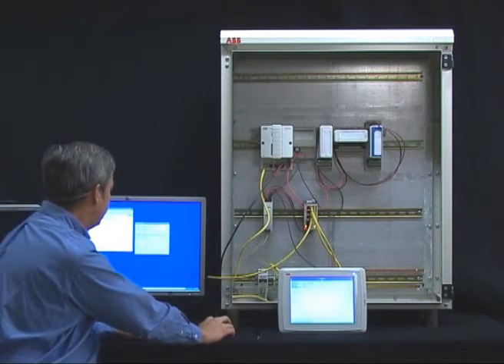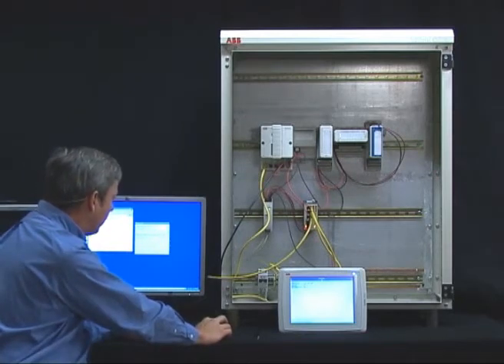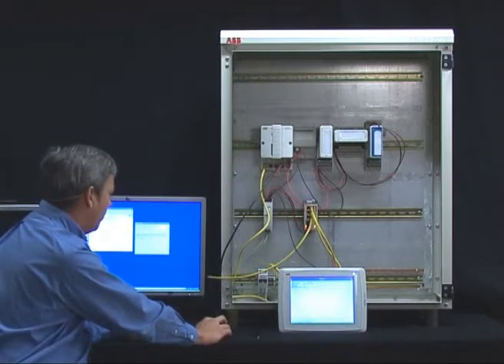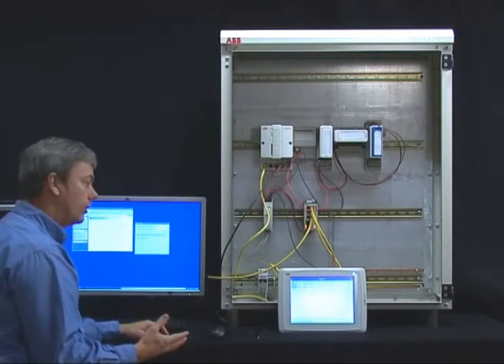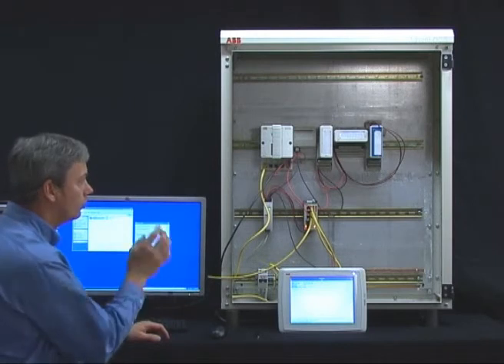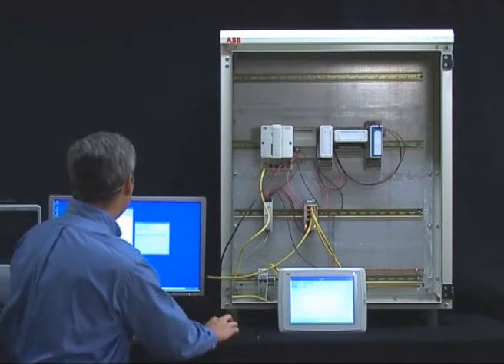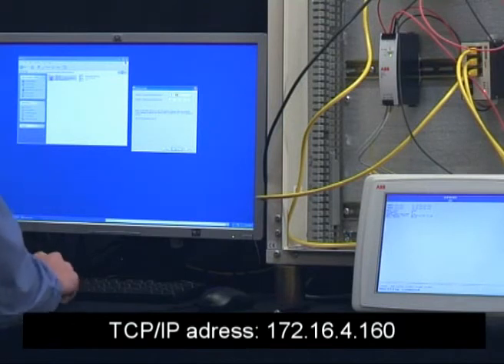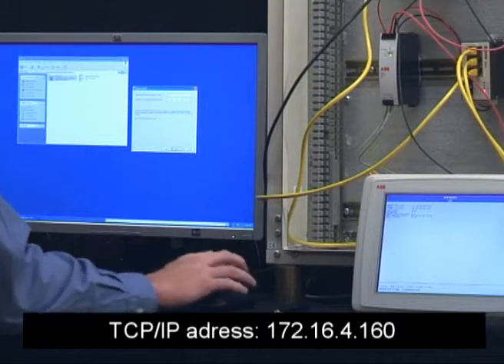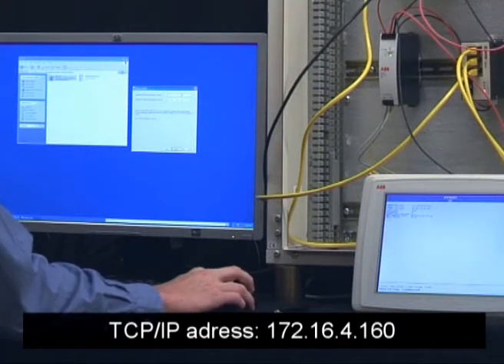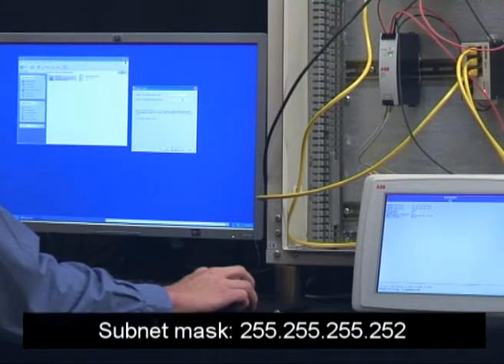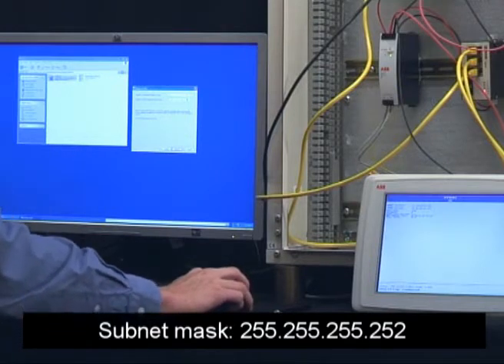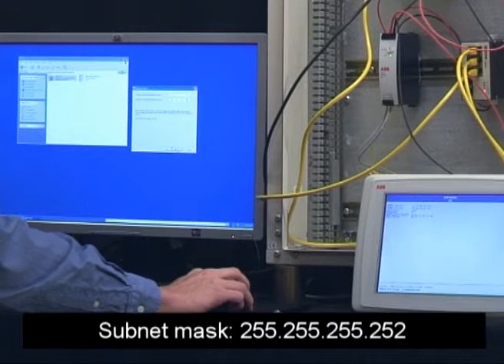We press next, and in the next step we can see the IP address and subnet mask that we would like to have in the panel after we have loaded the firmware. For the panel to be able to talk to the controller, it has to be on the same network. So we put it on 172.16.4.160 for instance, and the subnet mask has to be 255.255.255.252, just in the same way as for the compact HMI and the AC800M, and we press next.